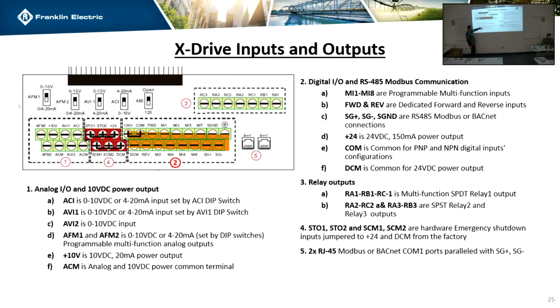AVI 2 is dedicated to 0 to 10. We have a couple of outputs, AFM 1 and AFM 2. Just like ACI and AVI, they're the same thing. They can do 0 to 10 or 4 to 20 output, but they're set by dip switches. And they're programmable, so when we go through the manual, we'll go through the options, but they're all multifunction, so you can change what they're referencing.